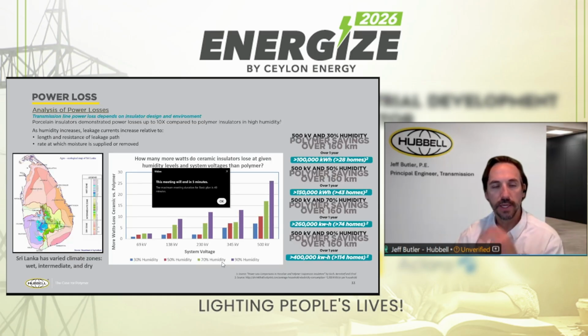Another test that we did was in regards to power losses. So we looked at across a range of voltages what the power losses across an insulator were relative to ceramics, a porcelain string, and a polymer string. And this is important because what we found is that it's based on voltage and humidity. So the data is collected in the table in the middle, but it's kind of broken down on the right side.